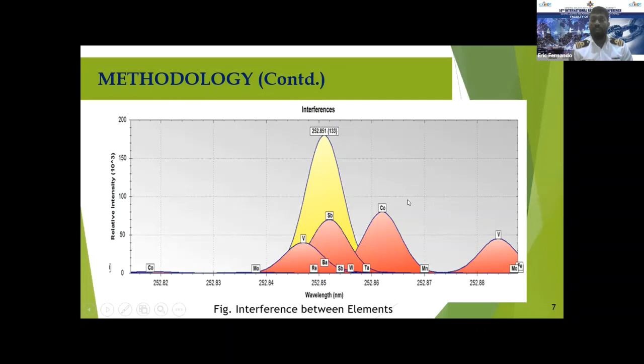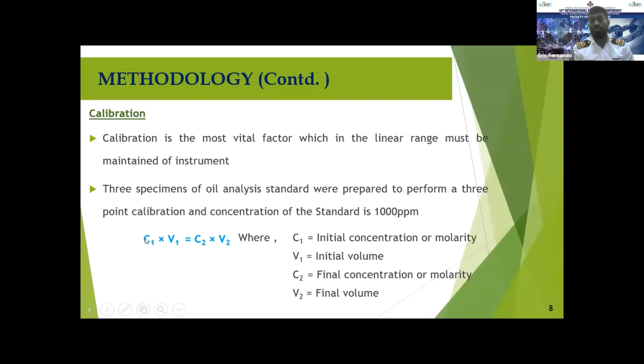So the second most important thing is the calibration, because we always have to make a linear range of the instrument. So prior to every analysis, we have to do a calibration. We are introducing 3 specimens of oil analysis standards, where we know the standard concentration of that particular sample is 1000 ppm. We have to prepare these 3 samples in order to have a 3-point calibration. For that, we have used the C1V1 = C2V2 formula. By using that, we have prepared 3 samples.